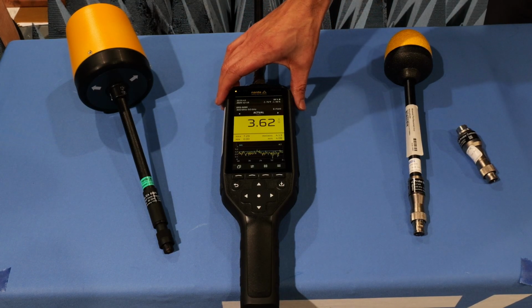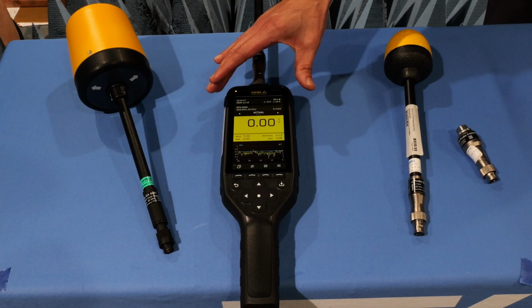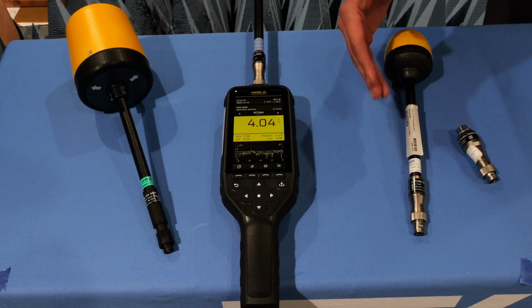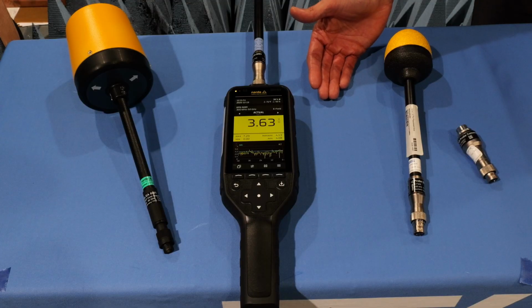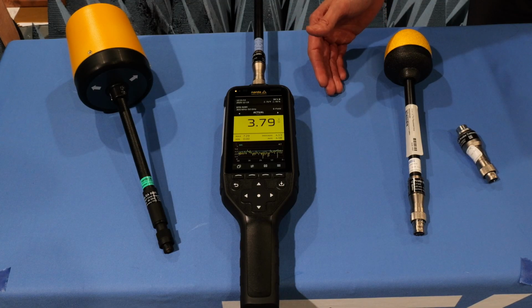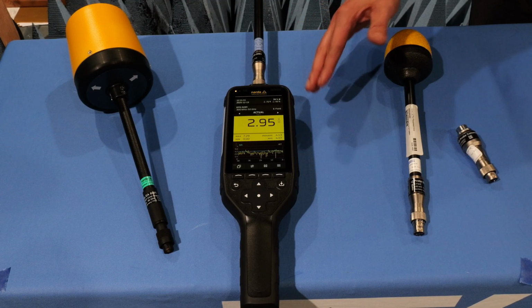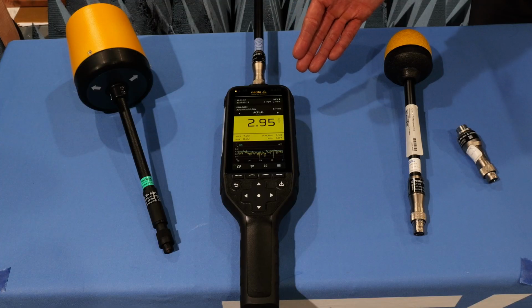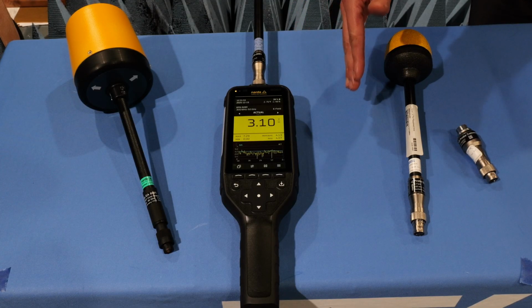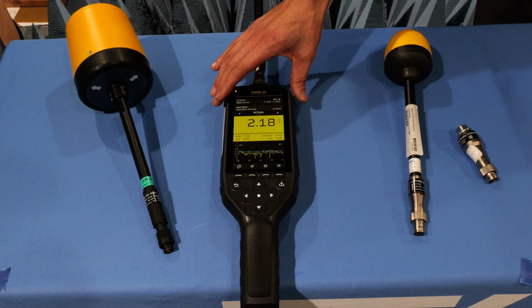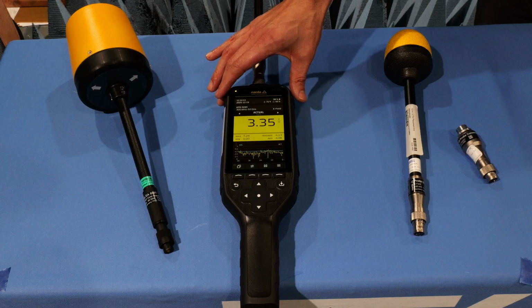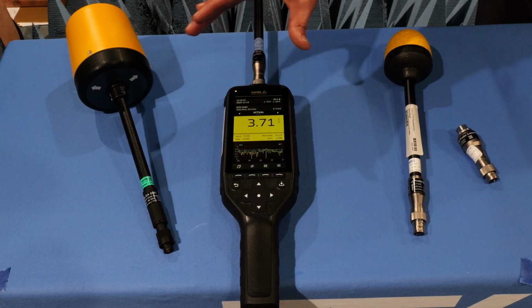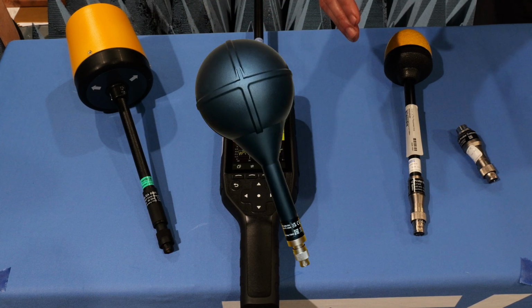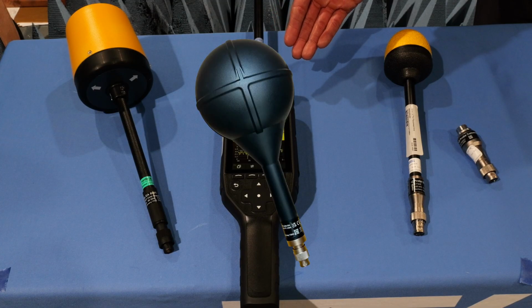The one nice thing about the new FieldMan is that it has replaced the old ELT 400 unit. In the past, if you wanted to take low magnetic field measurements, you needed two meters: the NBM series and the ELT 400. The FieldMan can do both, so you only need one meter for both measurements, and the probe you would need is the BFD 400 series probe.